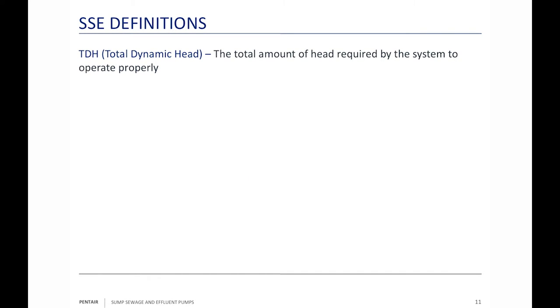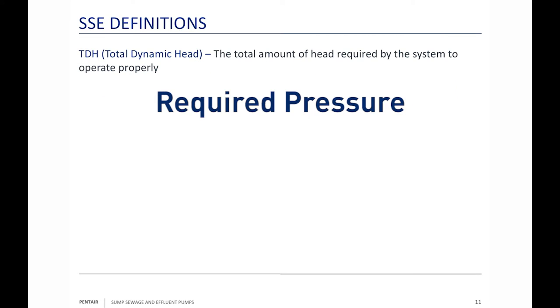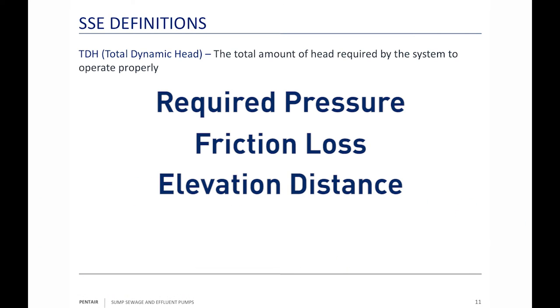TDH — total dynamic head — is a measure of all the energy required by the system to accomplish the task. It takes into consideration: pressure (for example, if pumping into a pressurized city system you must overcome that pressure at the curb stop), friction loss (how far away you're dumping the water, which adds up quickly if pipe sizing isn't careful), and elevation difference from the off switch to the highest point you have to pump. Those three things added together make your TDH.